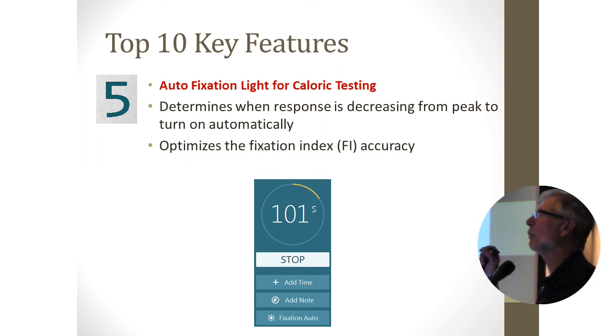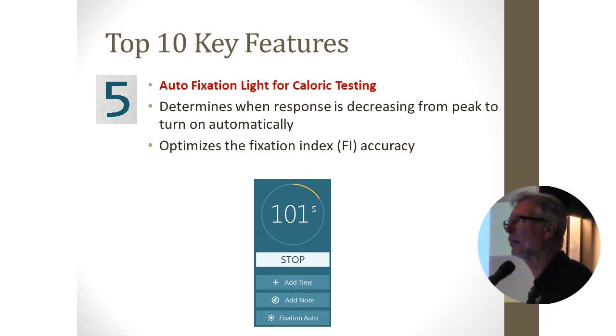But the problem is, what's the best time to do it? You don't want to do it when the nystagmus is at its peak, because you have to measure the slow phase velocity at the peak of the nystagmus response. So we have it where it's automatic now.